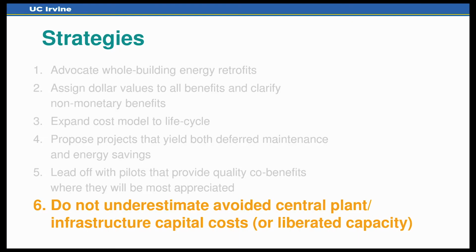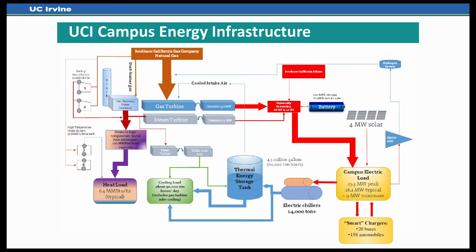So this one is a big one. It's actually bigger than we thought. It turns out that this cogeneration plant now, because of all the Smart Lab projects that we did, is way too big. We actually have an oversized cogen plant. We'll eventually need that because we're still a growing campus. We'll grow into this capacity. We have excess chiller capacity. We have 14,000 tons here and 2,000 tons over here. And this is all part of that same infrastructure.